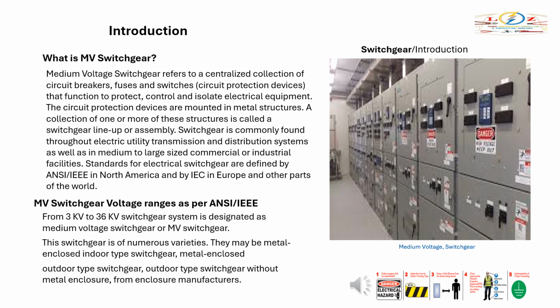Medium voltage switchgear refers to a centralized collection of circuit breakers, fuses, and switches, circuit protection devices, that function to protect, control, and isolate electrical equipment. The circuit protection devices are mounted in metal structures. A collection of one or more of these structures is called a switchgear lineup or assembly. Switchgear is commonly found throughout electric utility transmission and distribution systems, as well as in medium to large-sized commercial or industrial facilities.